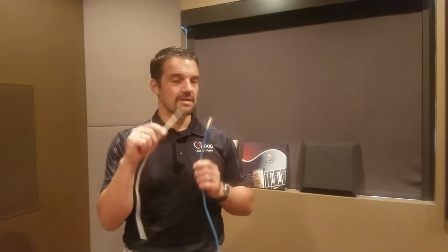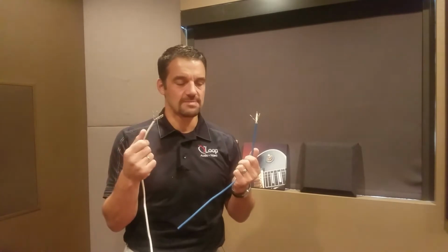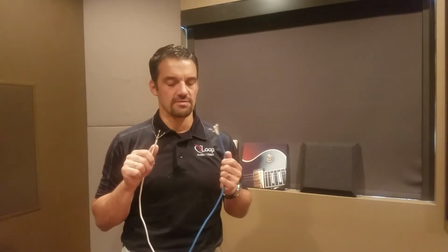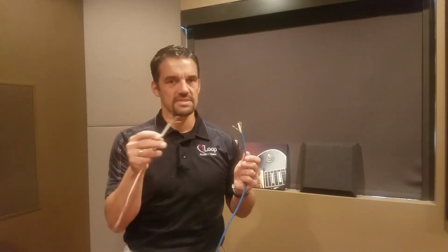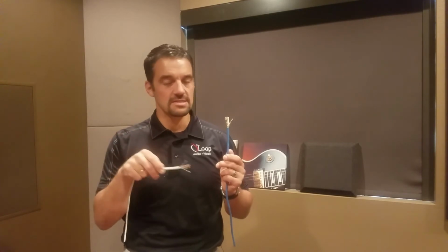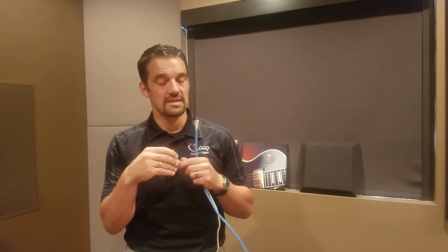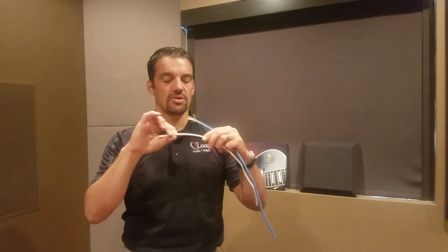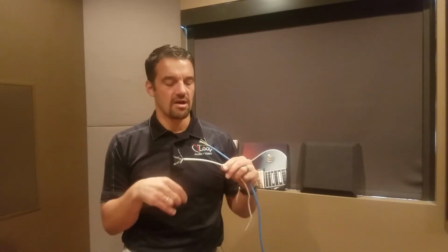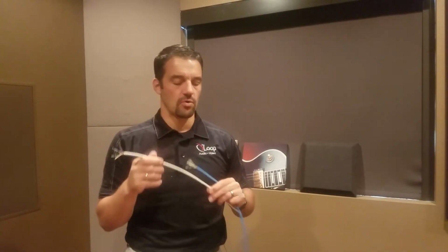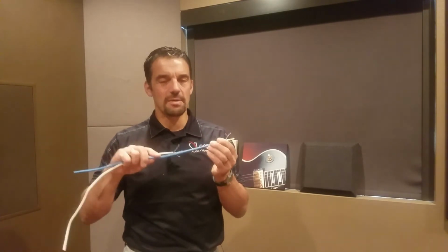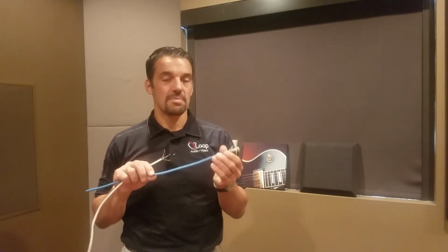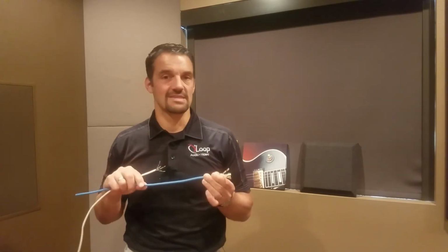So again, Cat 5, Cat 6, both support gigabit speeds. Both will do just fine in a residential environment. From a cost standpoint, if you're trying to save some money, use Cat 5. It pulls easier, so it's less expensive on the labor side for us to install. The connectors go on easier, so it's less expensive in that regard. It is smaller in diameter overall, so that's part of that cost decrease, and it's a little bit easier to pull and fit through holes. But if you do want a little bit better architecture in your home, you can go with Cat 6. Just recognize that you're not going to see a vast difference. I can tell you in our office, it's all wired with Cat 5.